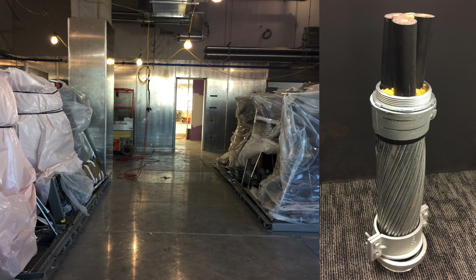So everything being 480, we didn't bring 480 up from the street. We brought it up at 13.8 kilovolts, and we're actually converting it to 480 on the floor. So that's a 13.8 feed. There's 2 of those, a primary and a backup feed coming up the building. That's the feed. If we did it at 480, we'd have 20 of those in each riser closet to get the same power up here.